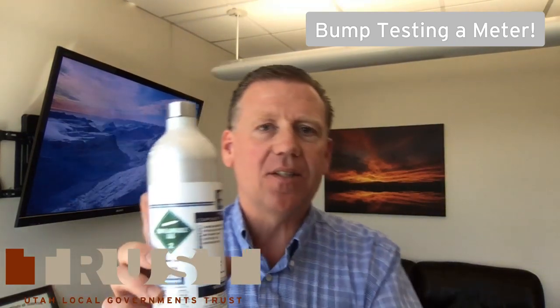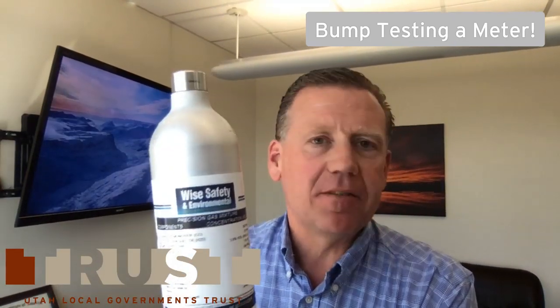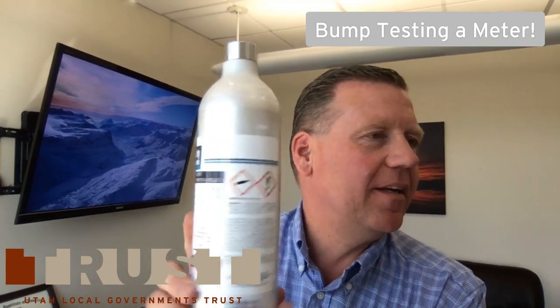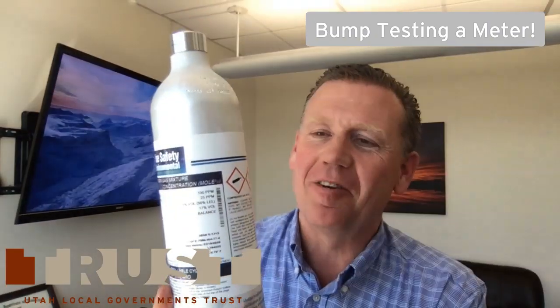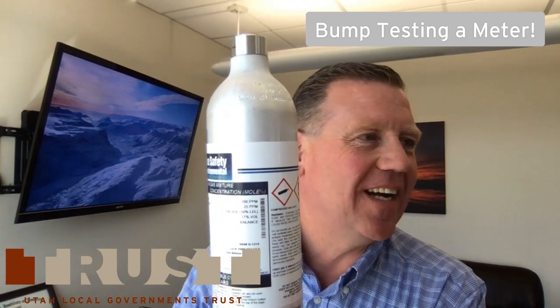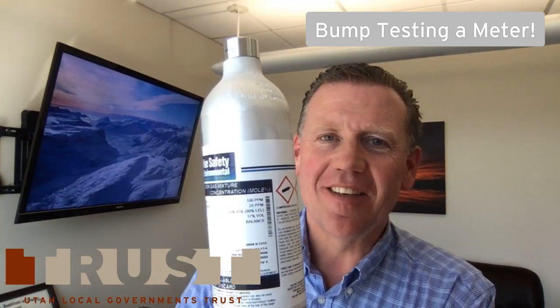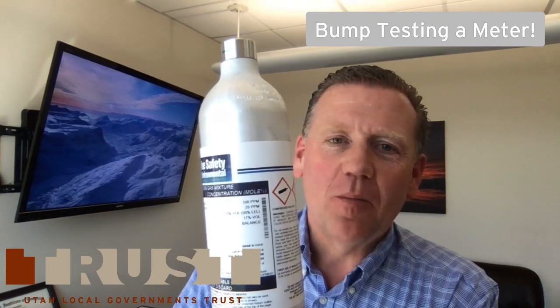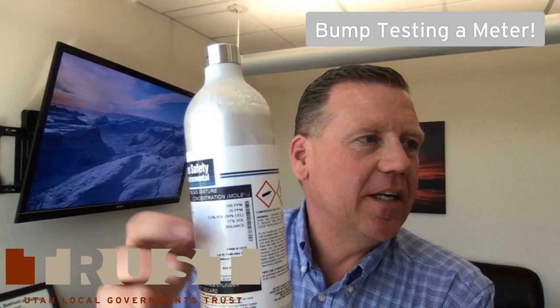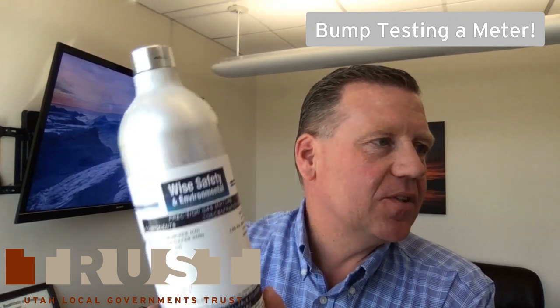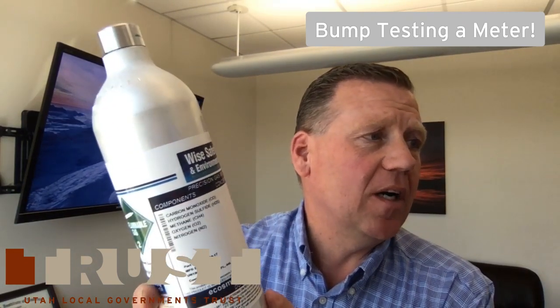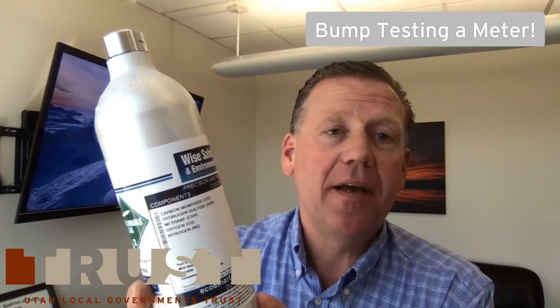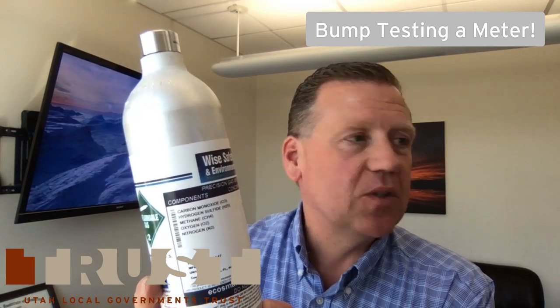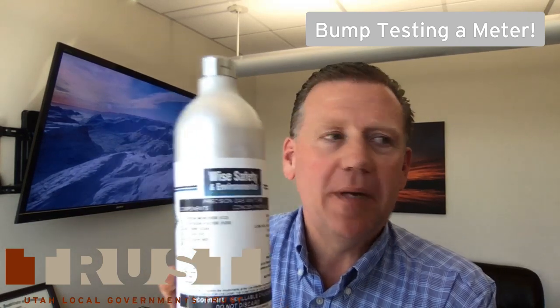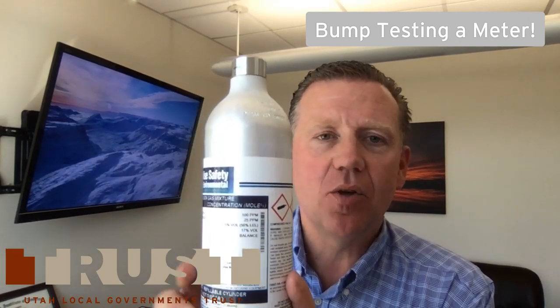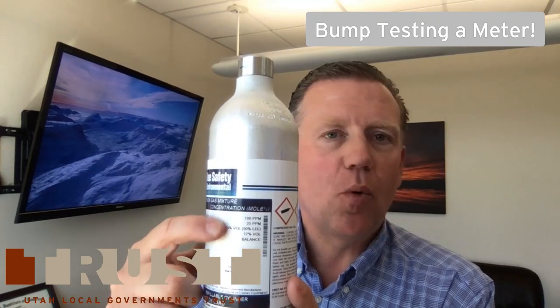We have a calibration gas. This is something you have to buy, and I'm not saying that the company we buy it from is exactly where to go. I'm not advertising for those guys, but they have taken good care of me here. This calibration gas, as you can see along here, has the various constituents that we're talking about: carbon monoxide, hydrogen sulfide, methane, that's for our lower explosive limit percentage, oxygen, and nitrogen is the balance there. And it's at set concentrations, so this is an important part to see.